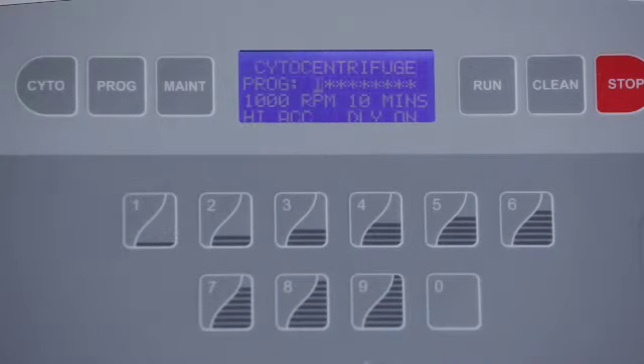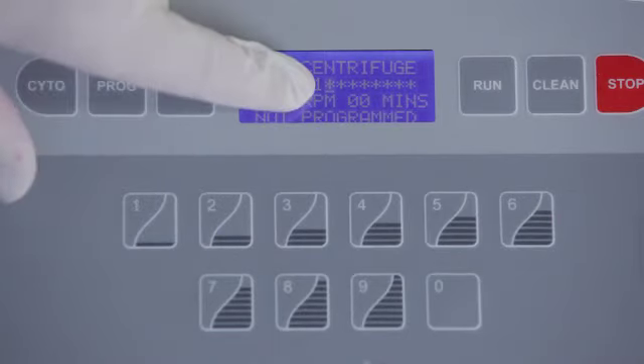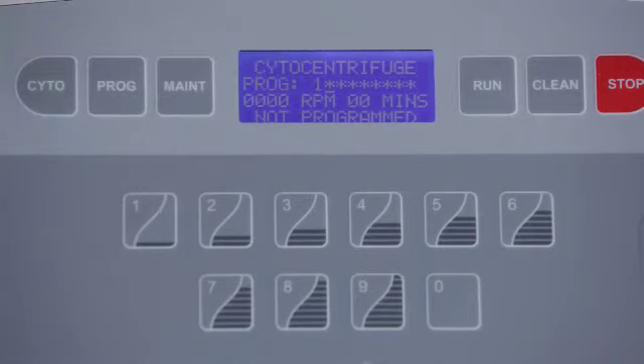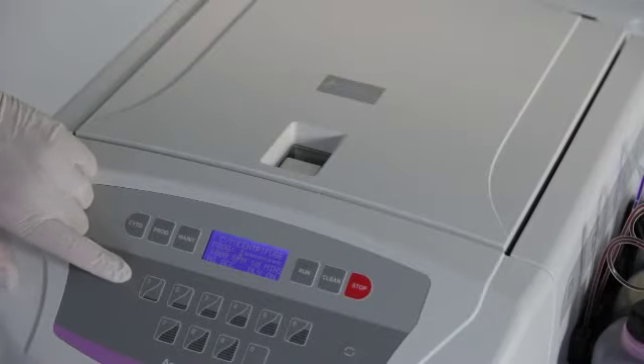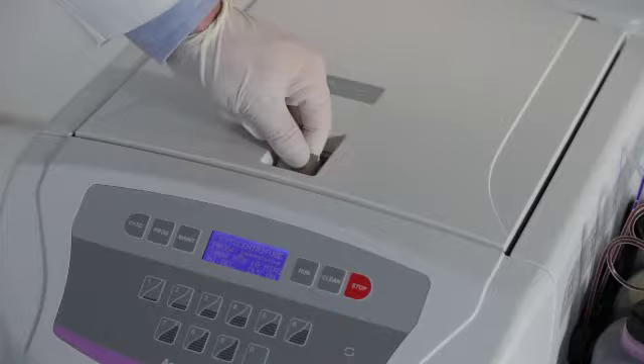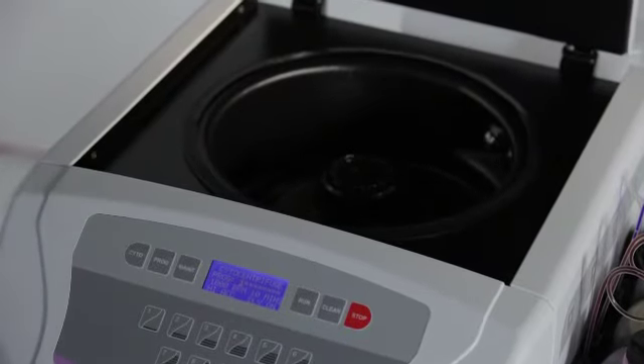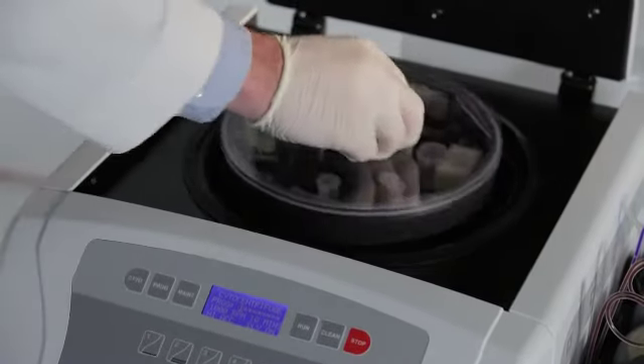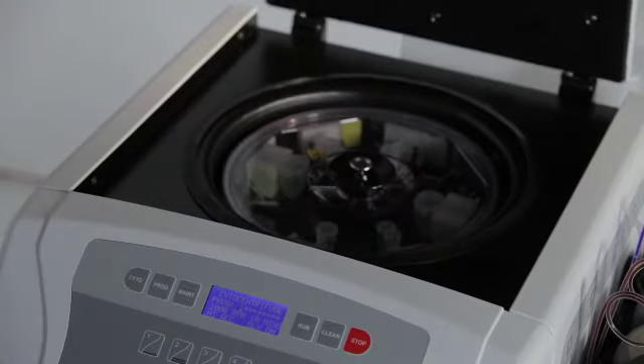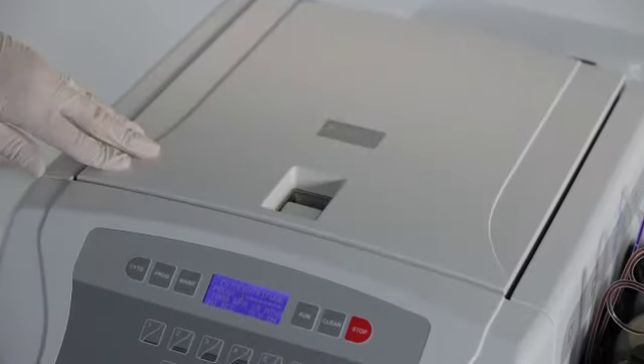The last option is for the lid lock delay. This option is set to off for the standard volume chambers, but it should be set to on for the Cyto Pro Magnum chamber. At the end of programming, this program is stored as the number 1 program until it is cleared or reprogrammed. The firmware allows for 9 programs to be set and stored. After programming, place the rotor in the stainer and press Run.